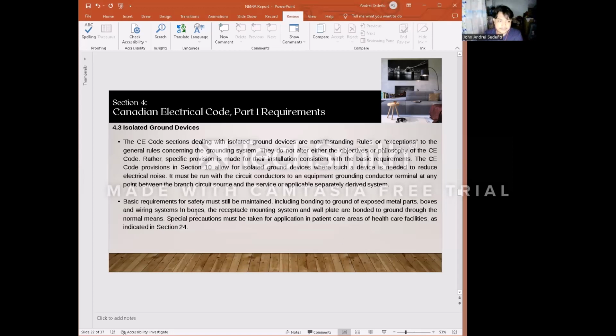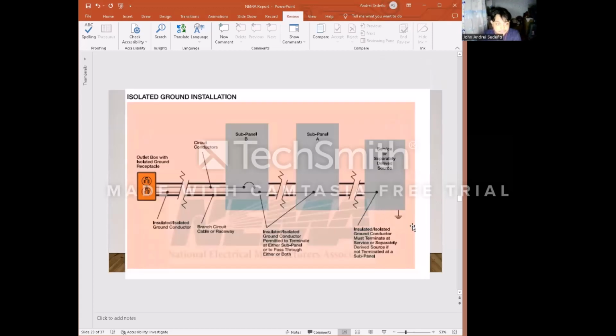Next, basic requirements for safety must still be maintained, including bonding to ground the exposed metal parts, boxes, and wiring systems in boxes. The receptacle, mounting system, and wall plate are bonded to the ground by normal means. Special precautions must be taken for application in patient care areas of health care facilities, as indicated in Section 24. This is the isolated ground installation.